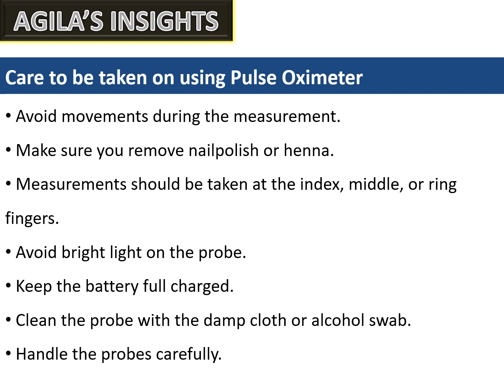Literature and hospital practices suggest that the pulse oximeter measurements should be taken at the index, middle or ring fingers, and that the measurements taken at these middle digits are equivalent. Avoid bright light on the probe, since the probe has soft rubber to shield it from light. Smoking may accumulate carbon monoxide and show a high reading. So keep the battery fully charged. Clean the probe with a damp cloth or alcohol swab. The probes are fragile, hence we should use them carefully.